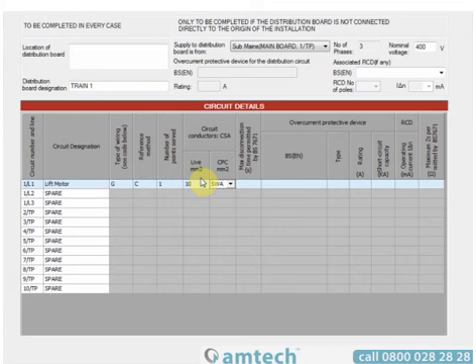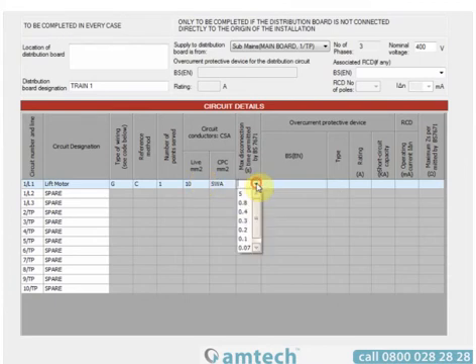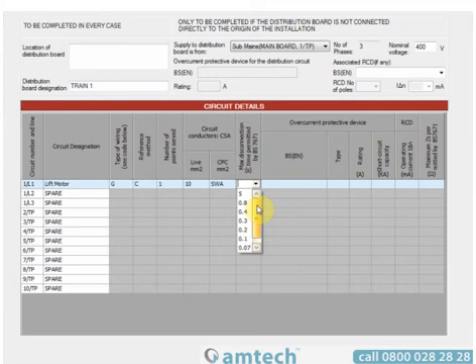You can also use the arrow keys on the keyboard to navigate through the certificate — the right arrow key will take you to the right and the left one to the left. The drop-down for maximum disconnection shows all the pre-entered values as stated in BS 7671. If you select a value that has a tabulated maximum ZS rating in BS 7671, you will automatically populate the maximum ZS permitted once you've selected the BS EN device and the rating.